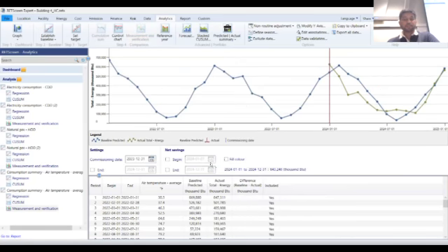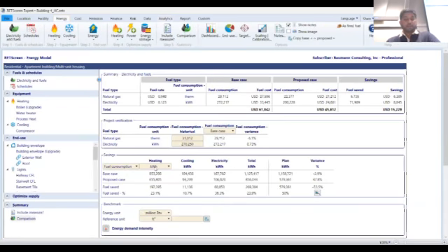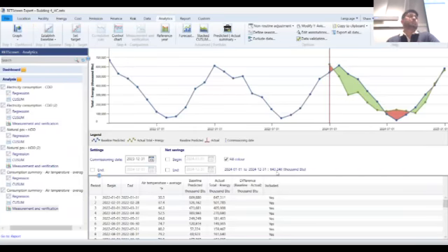Measurement and verification: 643,000 kBtus. Let's compare how we did on our energy modeling. This is the portion where you see the savings. I want to see it in 1000 BTUs. I predicted 919,000 kBtus of energy saved annually. Again, overestimated, and it's probably coming from the natural gas overestimation. But actually, we ended up saving about 643,000 kBtus. That's your actual real savings.